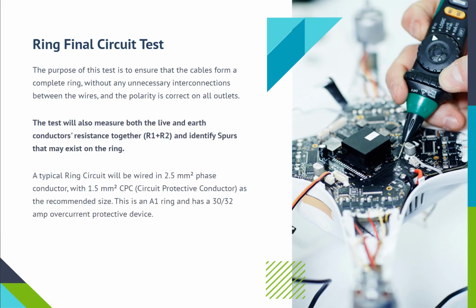Ring final circuit test. The purpose of this test is to ensure that the cables form a complete ring without any unnecessary interconnections between the wires, and the polarity is correct on all outlets. The test will also measure both the live and earth conductors' resistance together, R1 plus R2, and identify spurs that may exist on the ring. A typical ring circuit will be wired in 2.5 mm square phase conductor with 1.5 mm square CPC, circuit protective conductor, as the recommended size. This is an A1 ring and has a 30 or 32 amp overcurrent protective device.